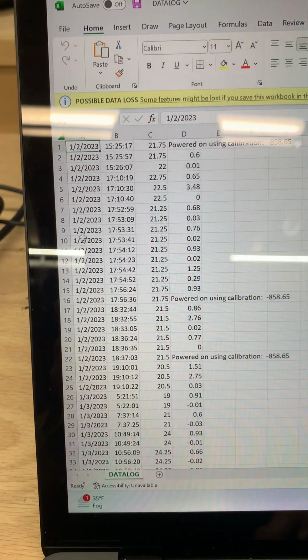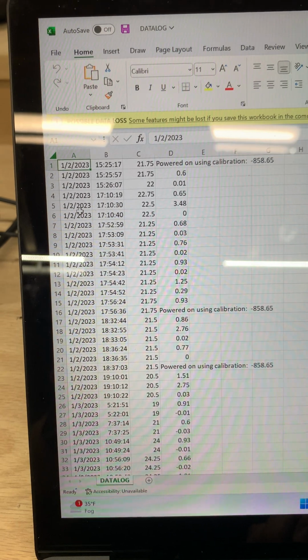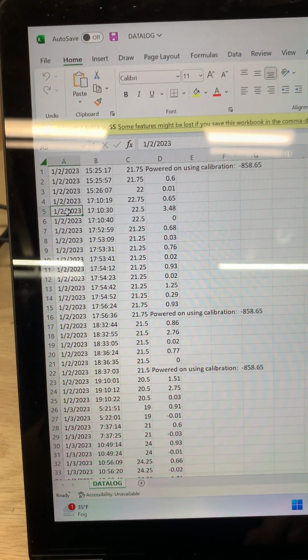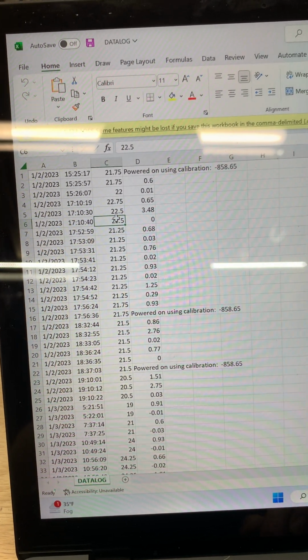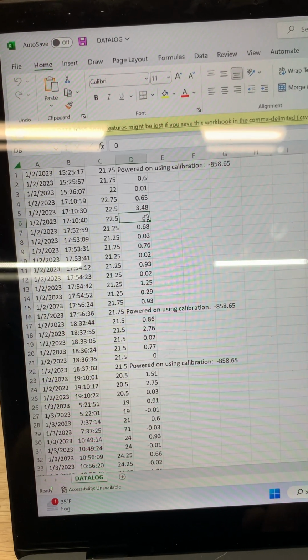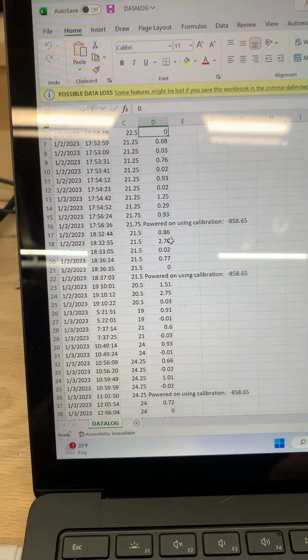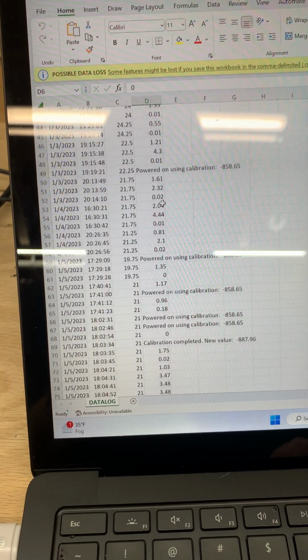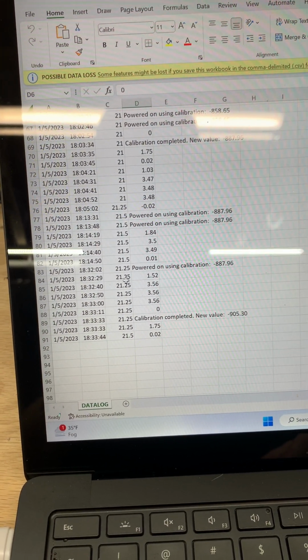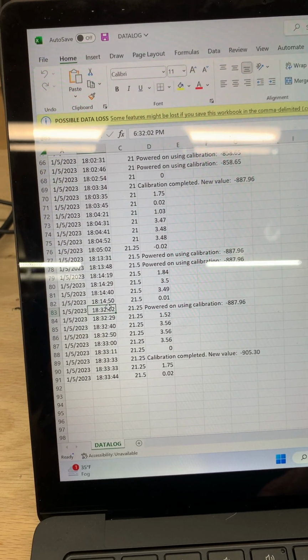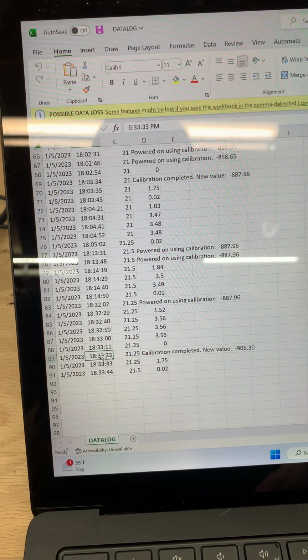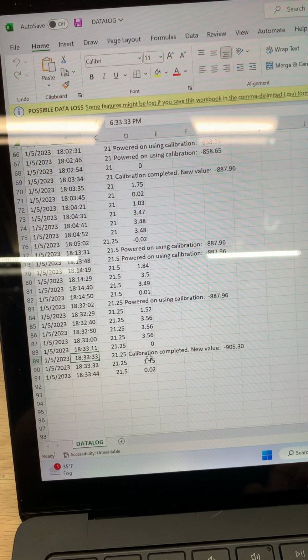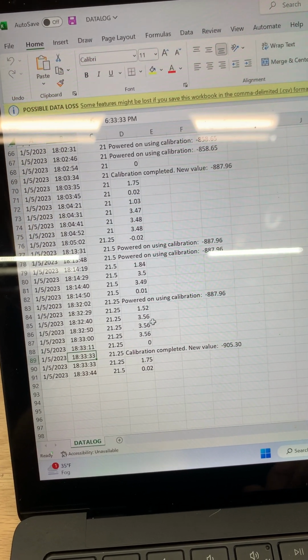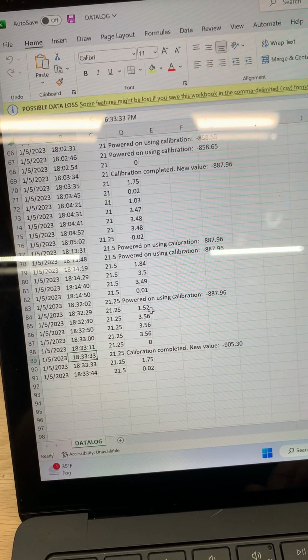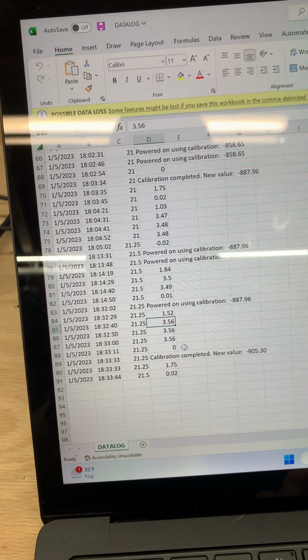Basically it's just going to make an entry every 10 seconds when there's a weight greater than 1/2 kilogram, with the date, the time, the temperature in Celsius, and the weight in kilograms. It also makes an entry when you power it on, or if you calibrate it. We should be able to see our calibration. We can see that we powered it on down here at 632 and we calibrated it at 633, and it shows what values it used for calibration. So that's kept in there. It shows the weight. You can see we put a weight on there of 3.56 kilograms.